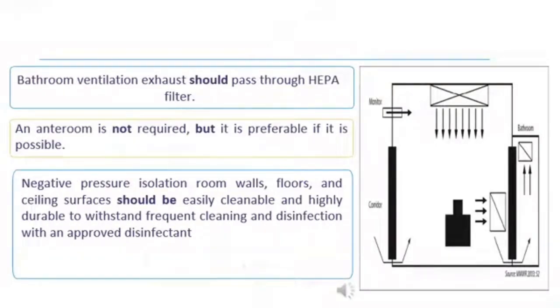In this type of room, the bathroom ventilation exhaust should pass through the HEPA filter. An anteroom is not required but is preferred or recommended if possible. Negative pressure isolation room walls, floors, and ceiling surfaces should be easily cleanable and highly durable to withstand frequent cleaning and disinfection processes with an approved disinfectant.